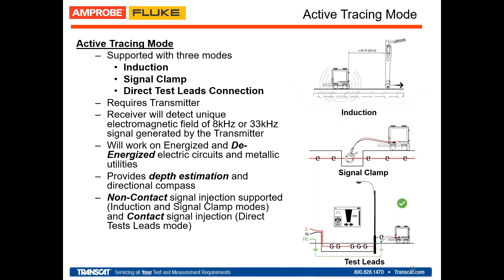This method is very popular but has been slowly replaced by induction mode, because with induction mode you don't need to make any direct connection to the circuit. Still, each has its benefits. Remember the underground locator has many modes, passive and active, each with pros and cons related to the structure of the circuit—whether you have one circuit or many overlapping circuits, radio frequency noise, or other AC signals at similar frequencies. Depending on that, there are many modes to choose from.